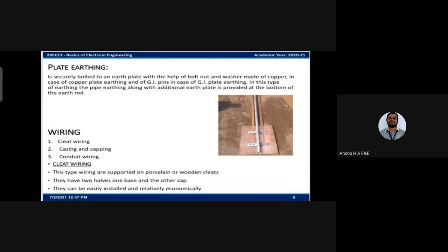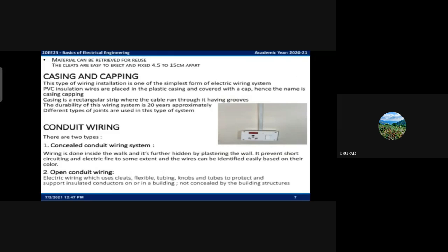Wiring types: cleat wiring, casing and capping, conduit wiring. Cleat wiring is the type where wires are supported on porcelain or wooden cleats. They have two halves, one base and the other a cap. They can be easily installed and are relatively economical. Casing and capping. This type of wiring installation is one of the simplest forms of electric wiring systems. PVC insulated wires are placed in the plastic casing and covered with a cap, hence the name capping. Casing is a rectangular strip where the cables run through its grooves. The durability of this wiring system is approximately 20 years.